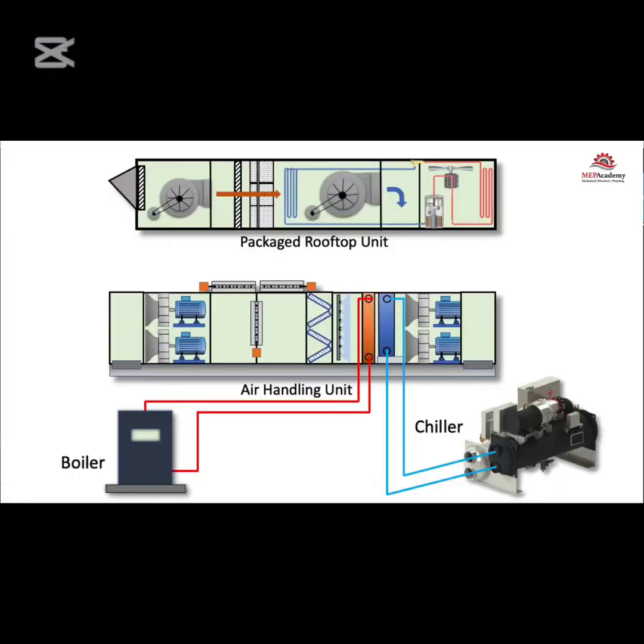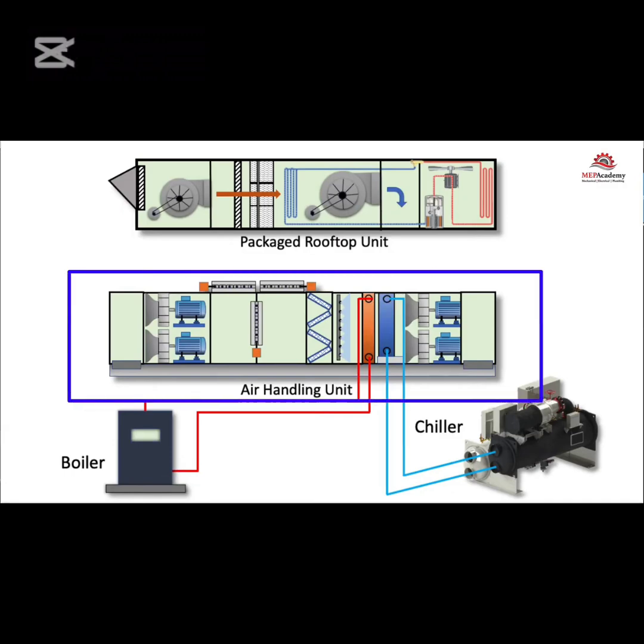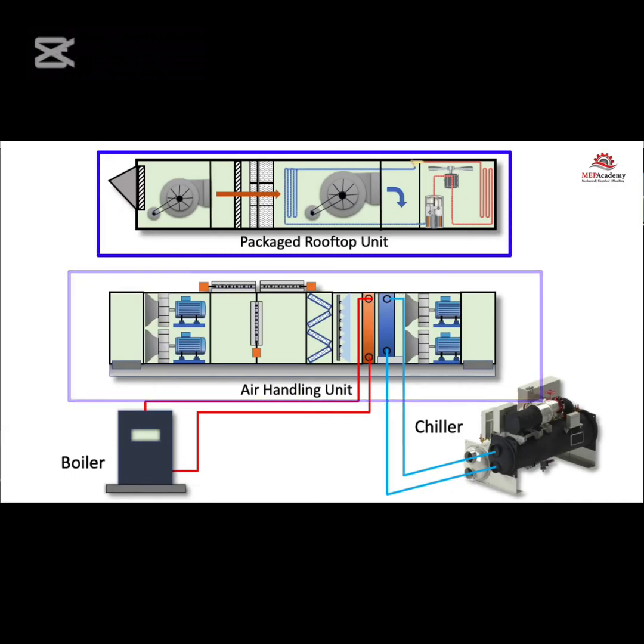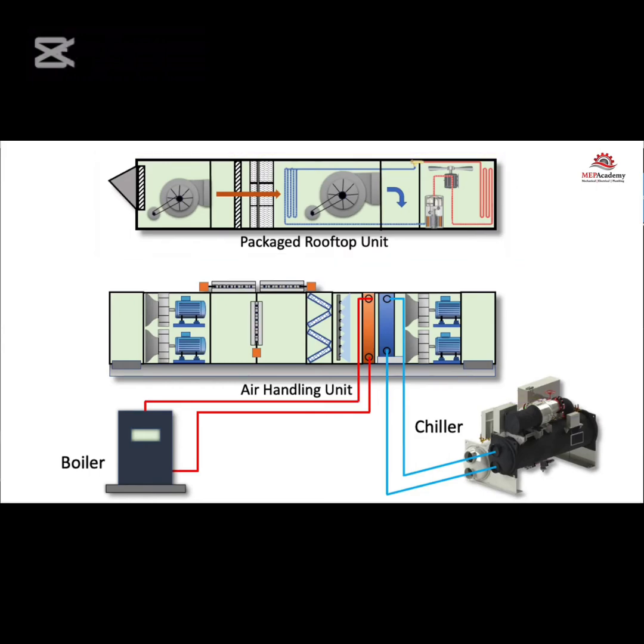The main differences between an air handler and your typical air conditioner is that the air handler doesn't provide the source for heating or cooling. Also, air handlers are available in much larger sizes up to and over 400,000 CFM. Air handlers allow greater customization to fit project specifics. The air handler will do its cooling using chilled water from a chiller or refrigerant from a remotely located compressor and do its heating using heating hot water or steam from a boiler.